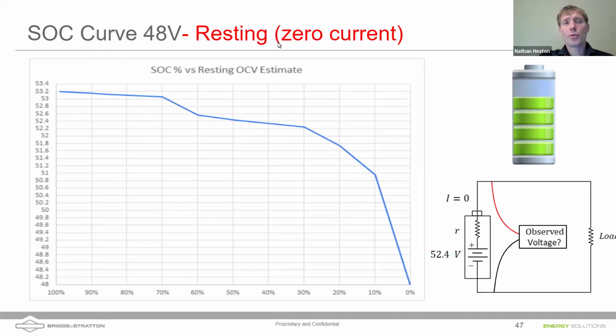This shows the state of charge for a resting battery. At about 99% state of charge, you should see an approximate voltage of 53.2 volts. As you discharge to lower states of charge, that voltage drops—at about 50% state of charge, a resting battery shows just over 52.4 volts. Eventually the voltage drops off fairly quickly: at 10% state of charge we're under 51 volts, and we can go all the way down to 48 volts, fully discharged, without damaging the battery.